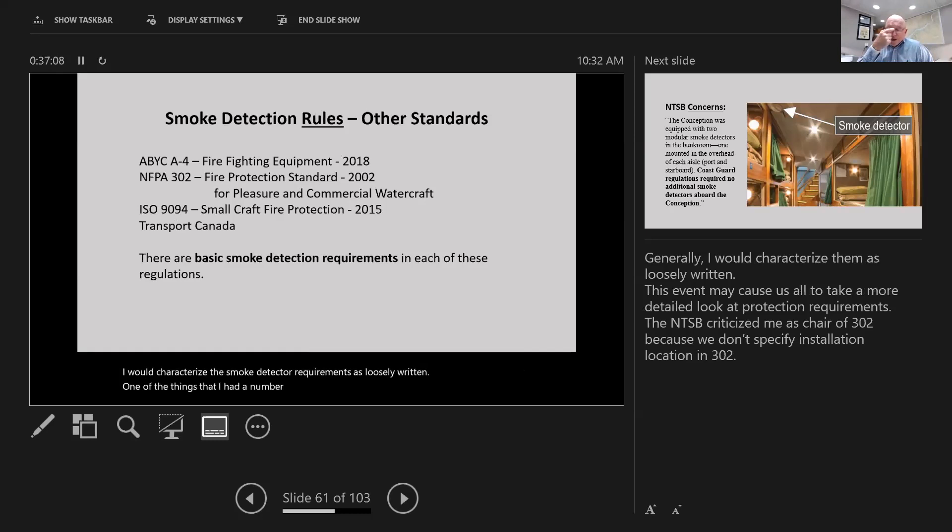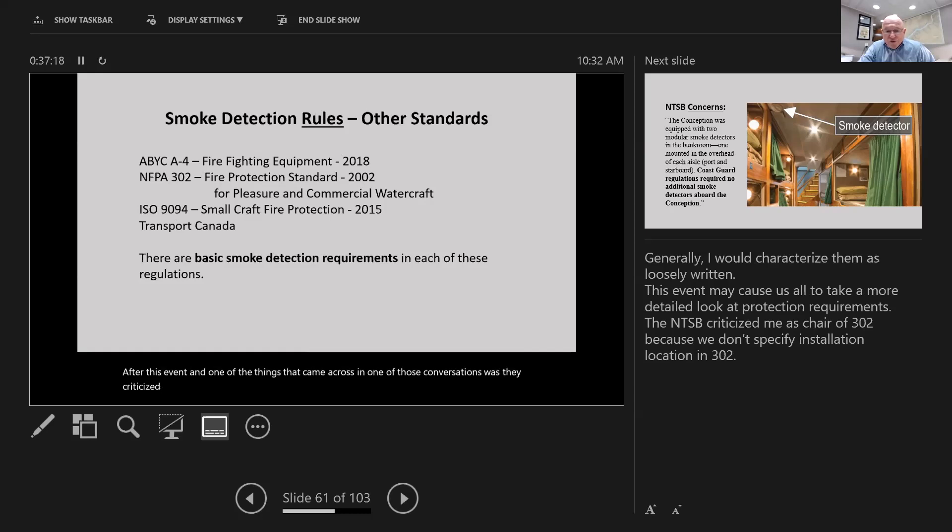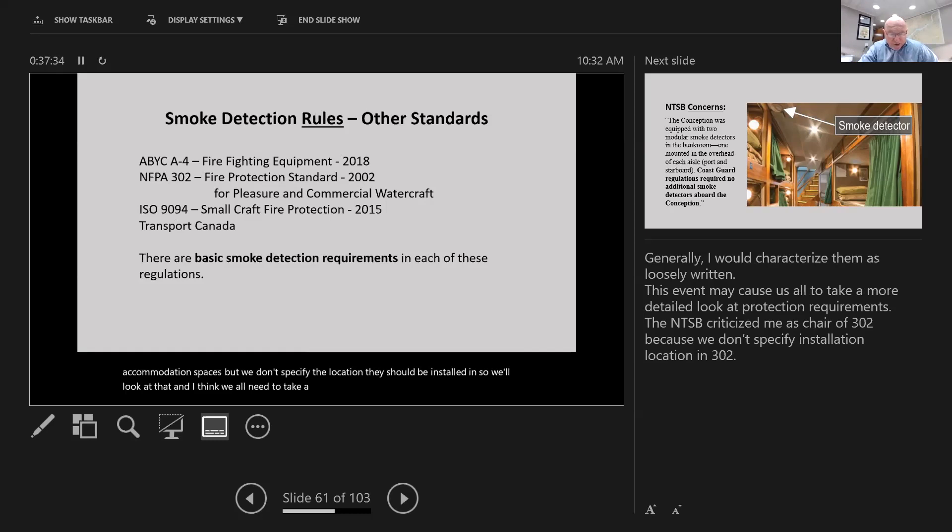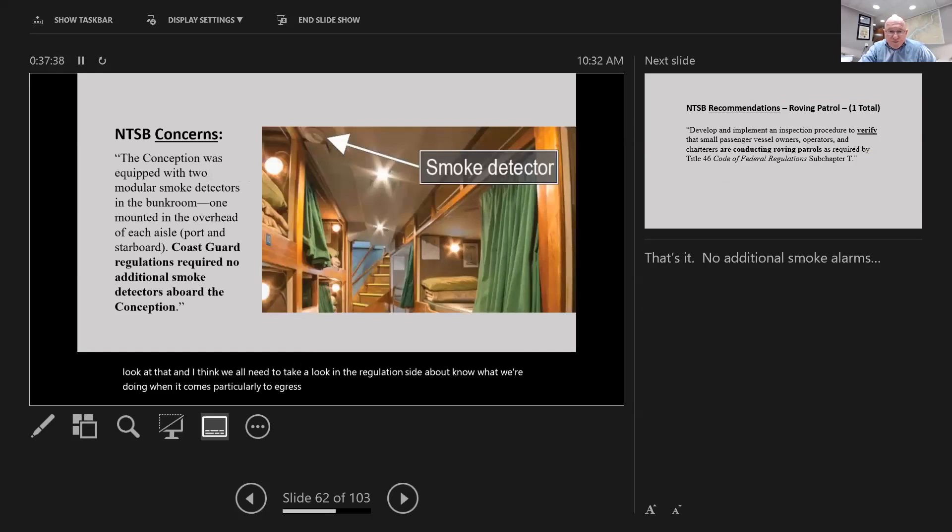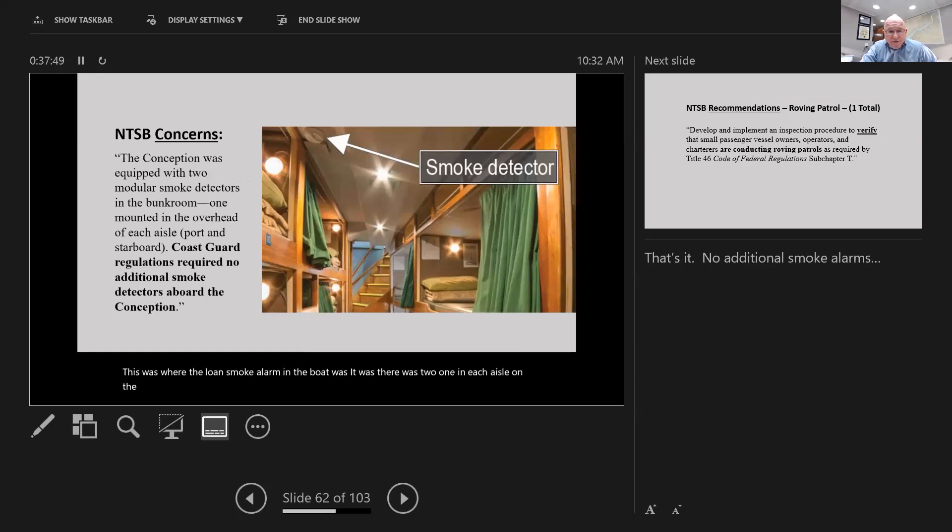The old subchapter T rules had no smoke detector requirements. The new subchapter T rules, as of 1996, required smoke alarms only in sleeping areas - just the bunk room. That requirement, even in 1996, was woefully inadequate. The ABYC got into the smoke alarm requirement game in 2018 because ISO put a standard in at 2015. NFPA 302 has had a smoke alarm requirement since around 2002, though loosely written.